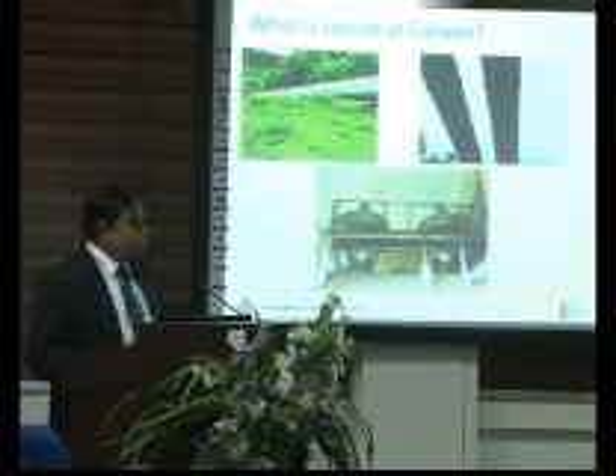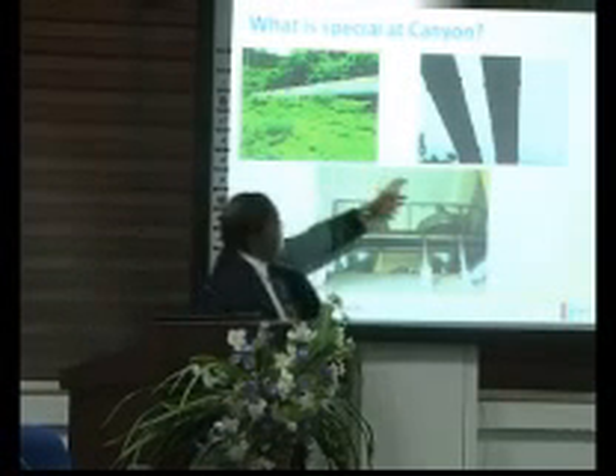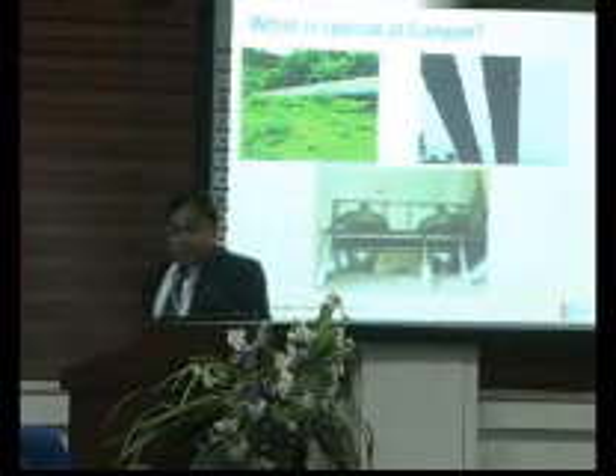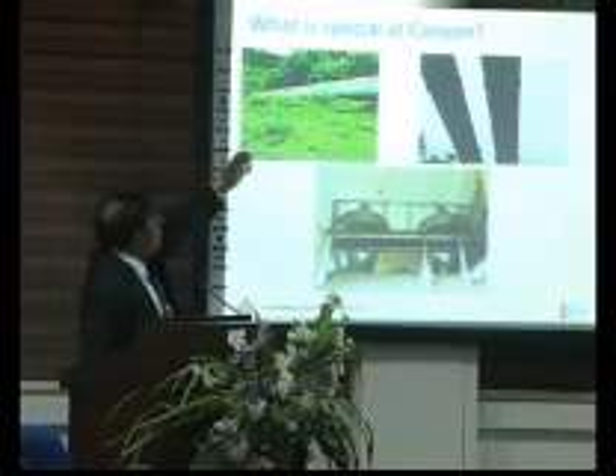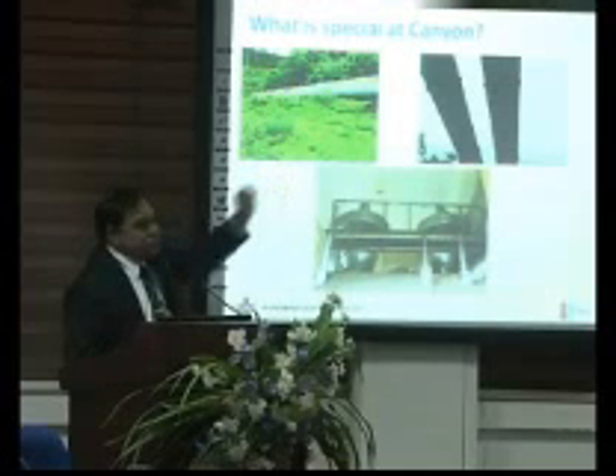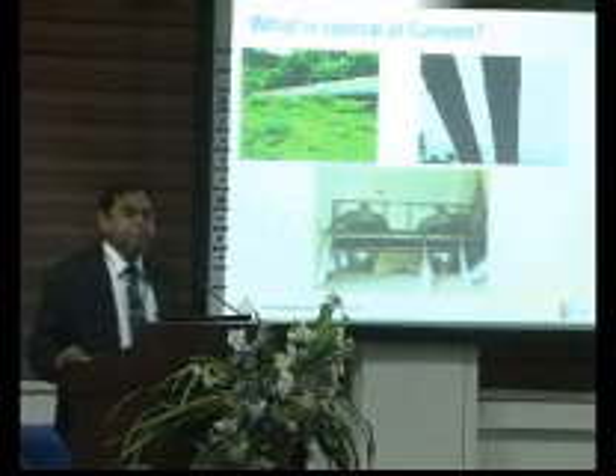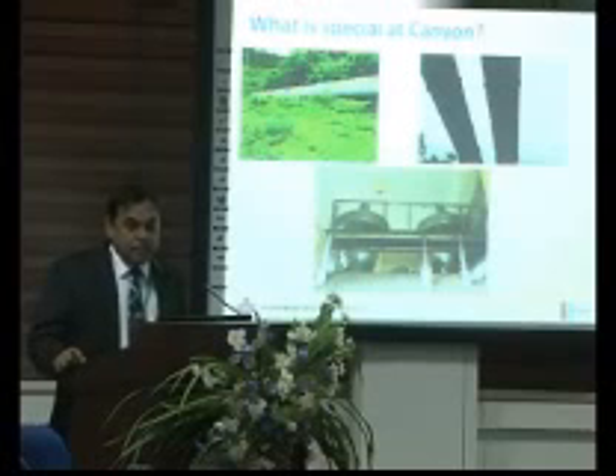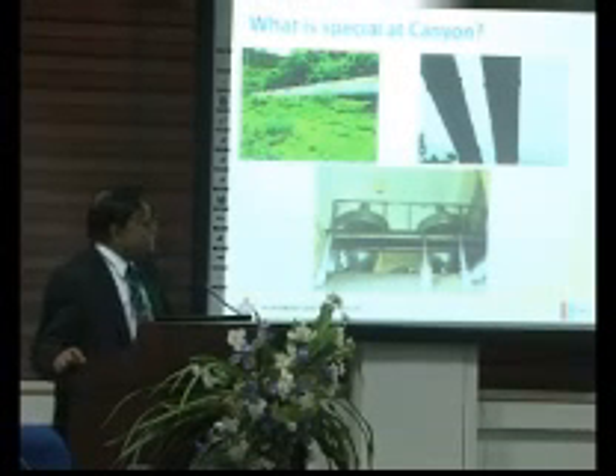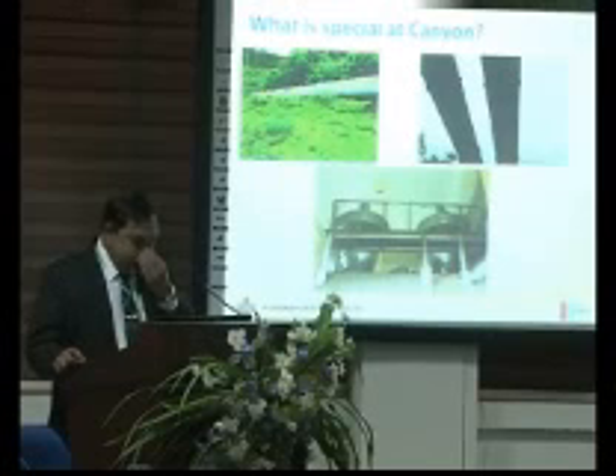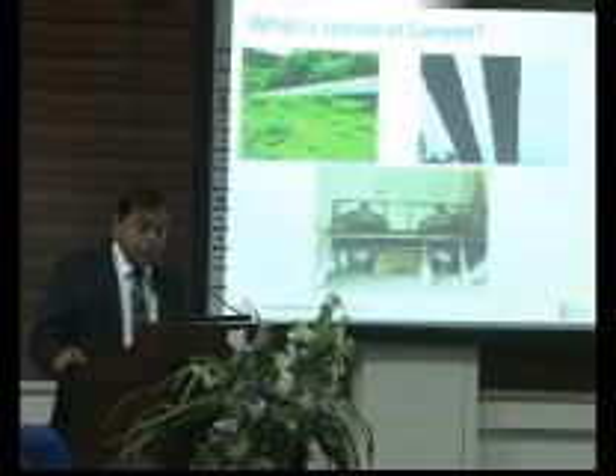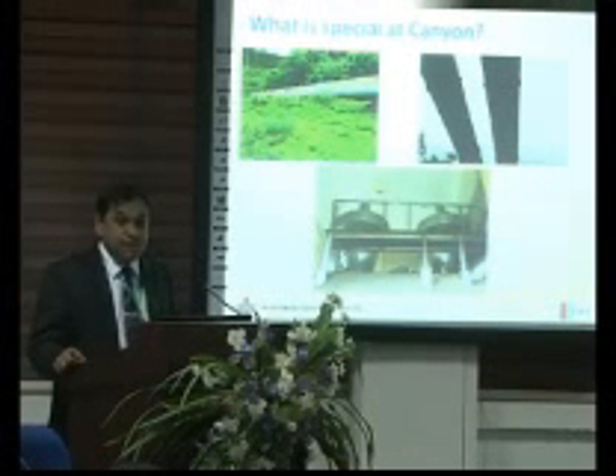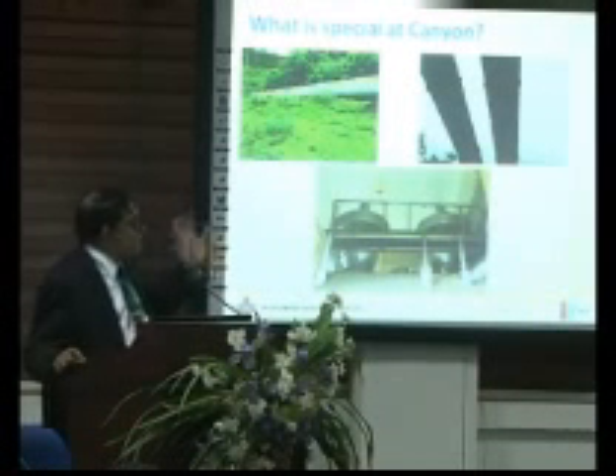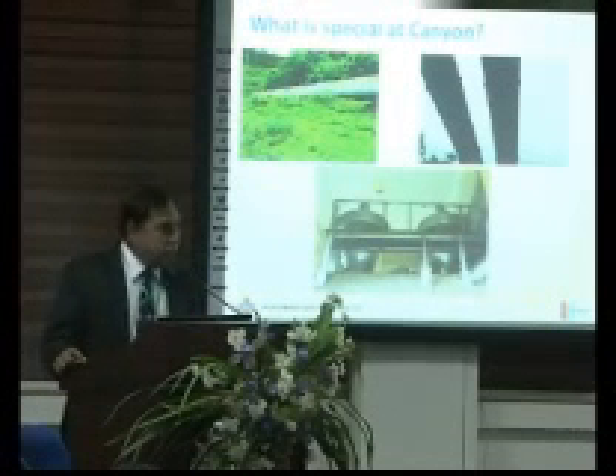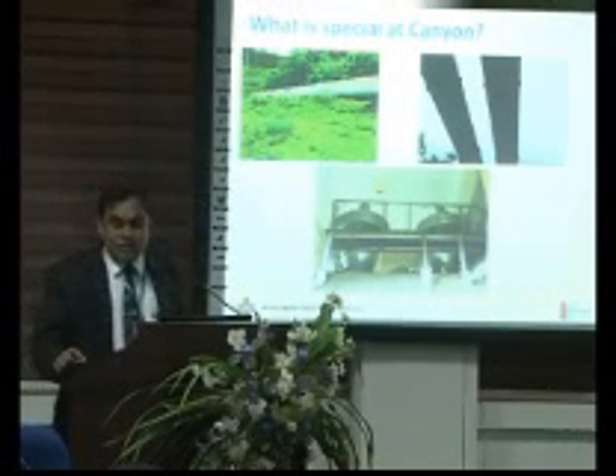So now, the water required for both penstocks at Canyon Power Plant is to be taken by one single tube of the same size as one of these penstocks, for a stretch of around 12 meters. So that causes severe head losses. And unfortunately, the plant can't take the full capacity due to this restriction. Of course, it is designed to take 60 megawatts. The maximum it can take is around 50 megawatts because there is a severe head loss here.